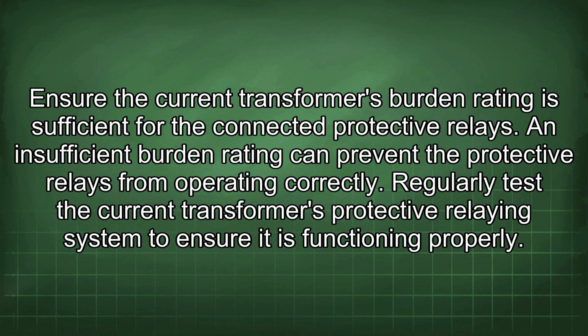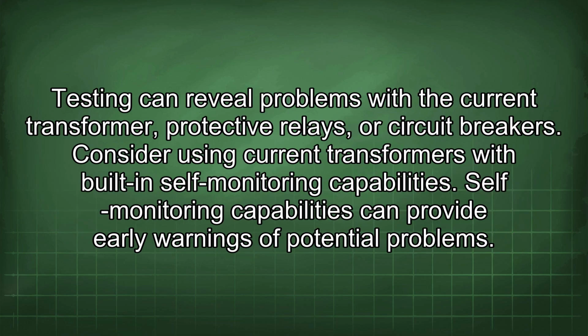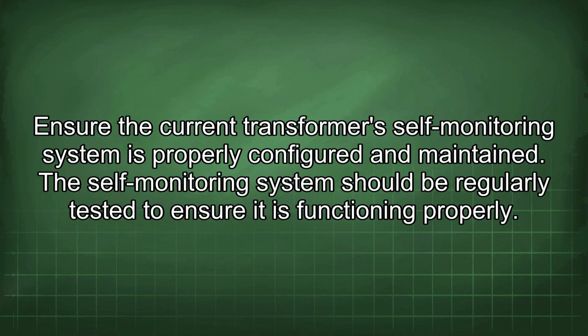Regularly test the current transformer's protective relaying system to ensure it is functioning properly. Testing can reveal problems with the current transformer, protective relays, or circuit breakers. Consider using current transformers with built-in self-monitoring capabilities. Self-monitoring capabilities can provide early warnings of potential problems. Ensure the current transformer's self-monitoring system is properly configured and maintained. The self-monitoring system should be regularly tested to ensure it is functioning properly.